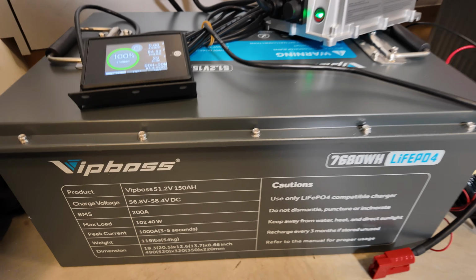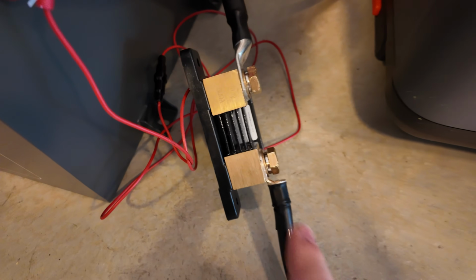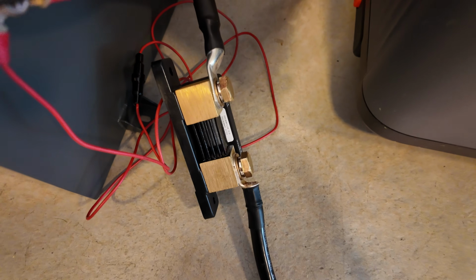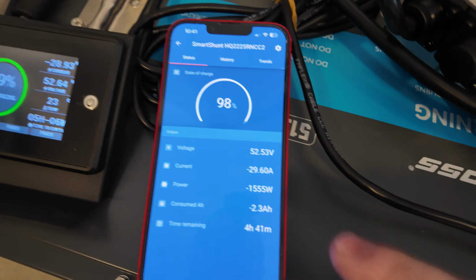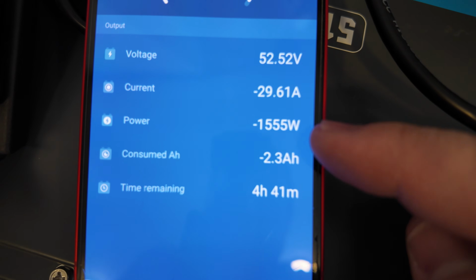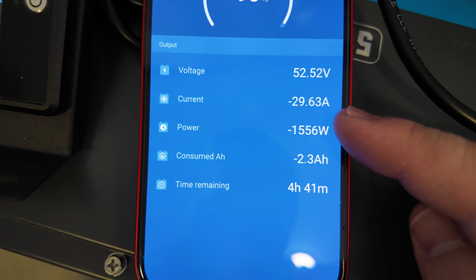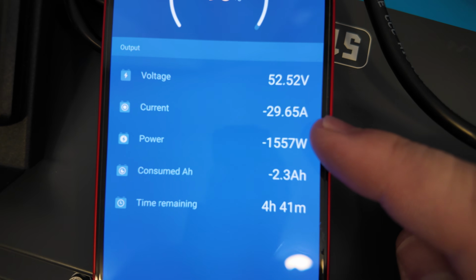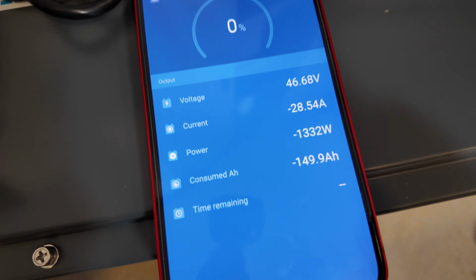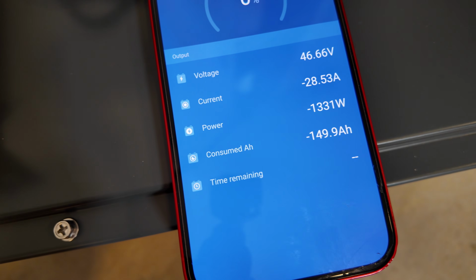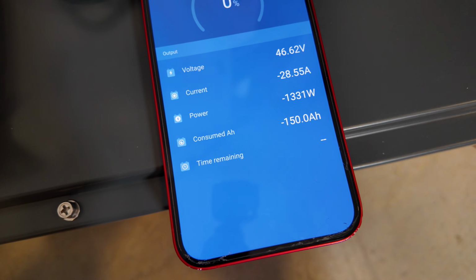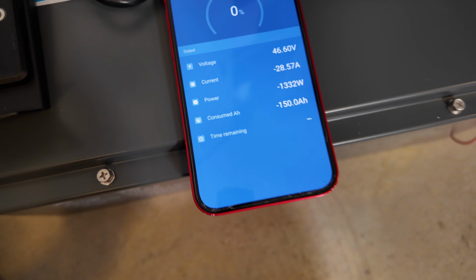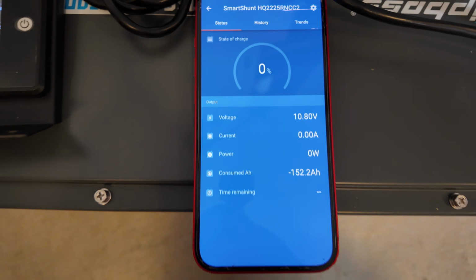Battery capacity test on this Vipboss. We're going to be metering things through the Victron SmartShunt here. A 0.2 C rate of discharge for a 150 amp hour battery would be about 30 amps. You can see we're right there. Okay, coming down the home stretch here, 149.9, and there's 150 amp hours right there. So full capacity. Okay, it just tripped offline.